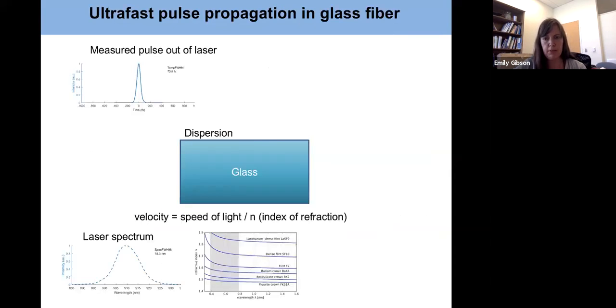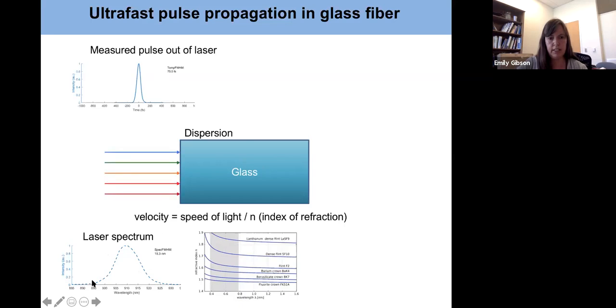Okay. Another issue I wanted to talk about that we run into is that these endoscope fiber bundles are not meant for multiphoton imaging. So it's a challenge to try to do multiphoton imaging through a meter-long glass fiber. One of the things that happens is dispersion. You're trying to propagate a short laser pulse through a 1.5 meter piece of glass. The pulse coming right out of your Ti-sapphire laser is about 70 to 100 femtoseconds in duration, and it has a certain spectrum, let's say about 15 nanometer spectral width.